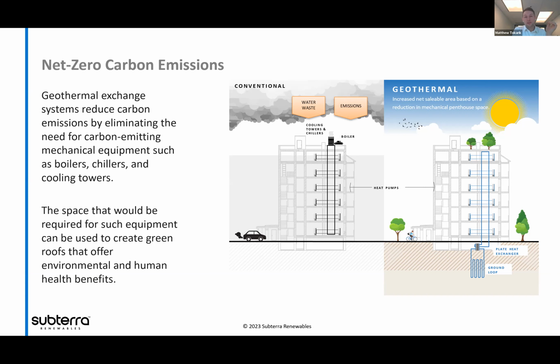So when we're going from an efficiency of a boiler at 90% up to an efficiency of a ground source heat pump at 400%, we've got a really big jump in energy efficiency, which translates into a drastic reduction in energy consumption in the building. That's how we get to that low energy use intensity.